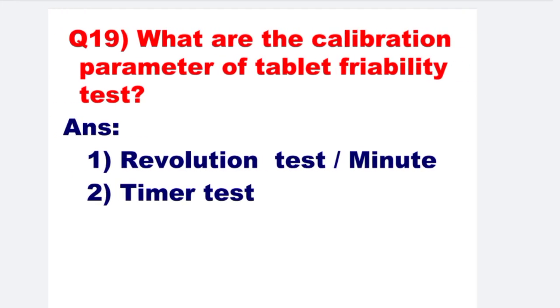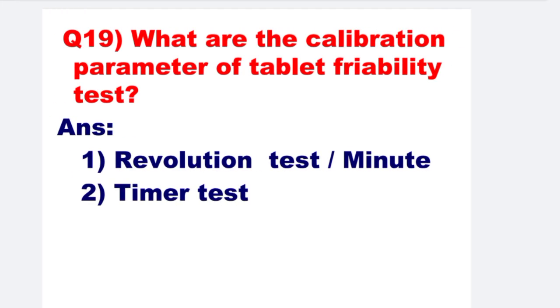Next: What are the calibration parameters of tablet friability test? There are two parameters for the calibration of the friability test. Number one is revolution test per minute, and number two is timer test.